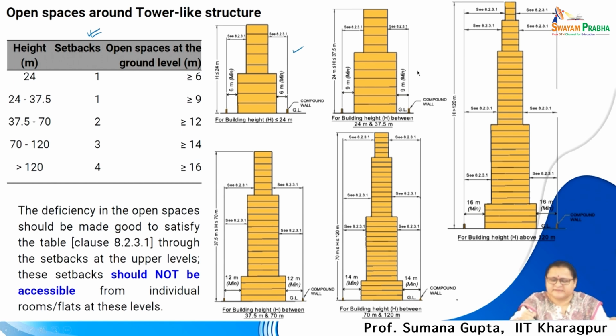If I have one setback, but beyond 24 to 37.5 meters, it will require 9 meters. Beyond 37 meters to 70 meters, if it has two setbacks, that is this picture, it will be 12 meters, and after that 70 to 120 meters, if it has 3 setbacks, it will be 14 meters, and more than 120 meters and having 4 setbacks, it will be 16 meters at the ground.